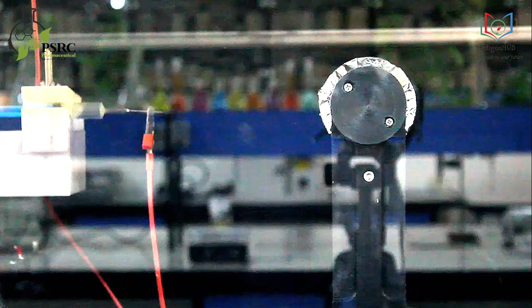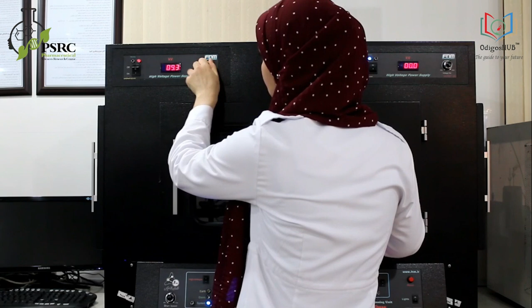The last crucial parameter is time. The time, as well as other parameters, is related to your method, your needed fiber and your application. At the end of your estimated time, you should just press the run stop key to stop the process. It's here. Then we gradually decrease the voltage. Okay. After that, at first, turn off the upper switch, then the bottom one. Okay. Release the crocodile clip for the needle and turn off the front switch.